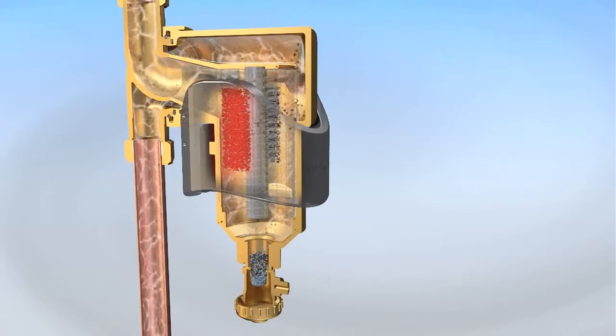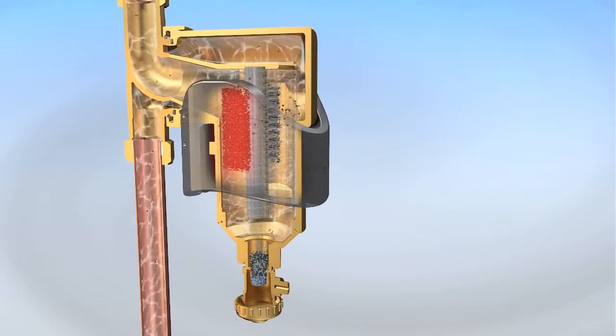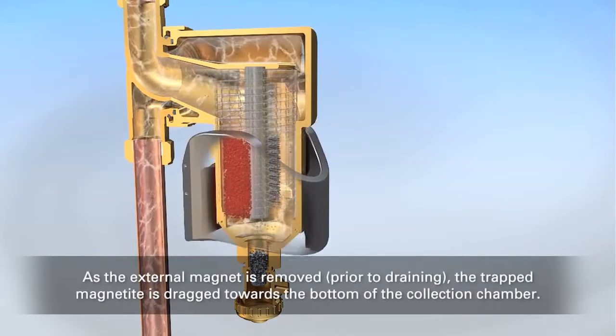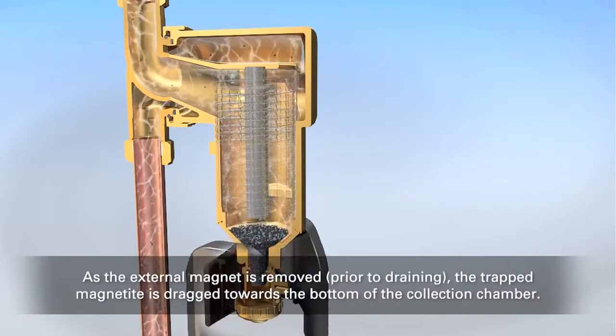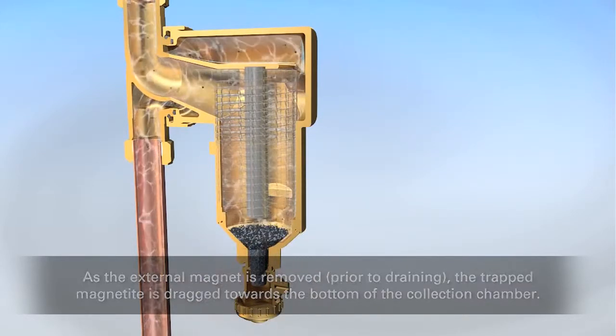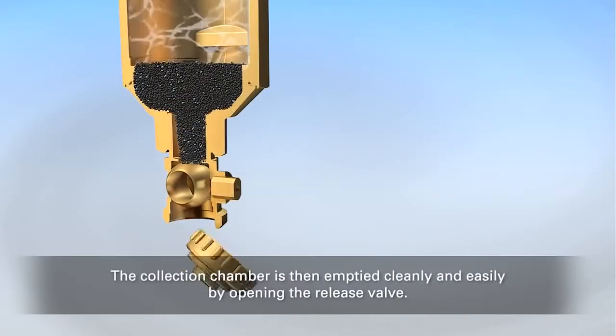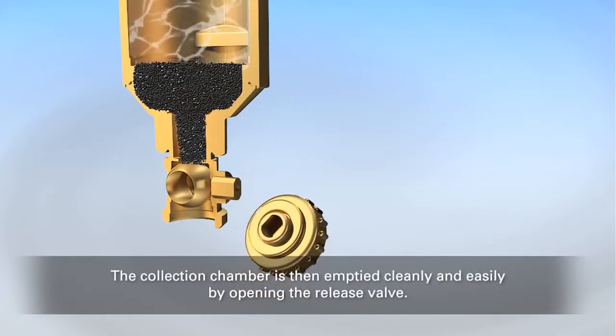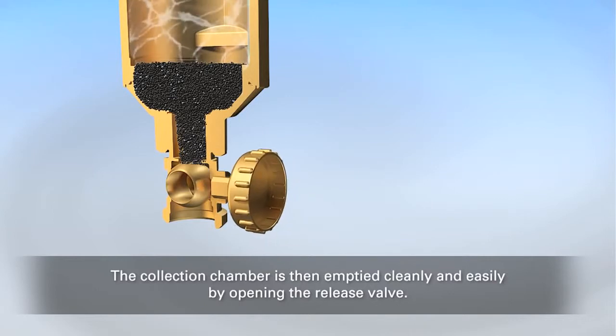Prior to draining the SpiroTrap MB3, the magnet should be slid down and off the unit. This action drags the collected magnetite to the bottom of the collection chamber. The collection chamber can then be emptied cleanly and easily by opening the release valve.